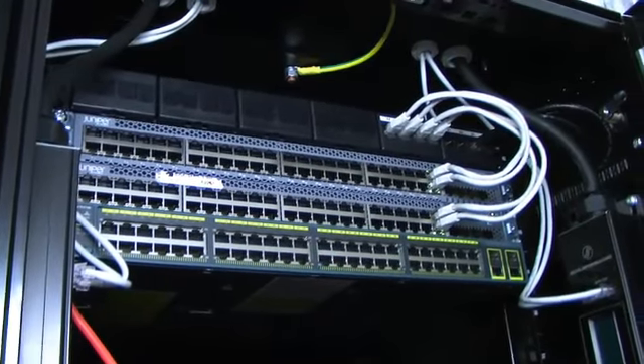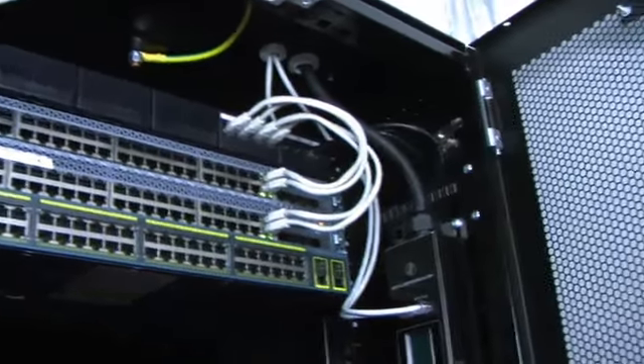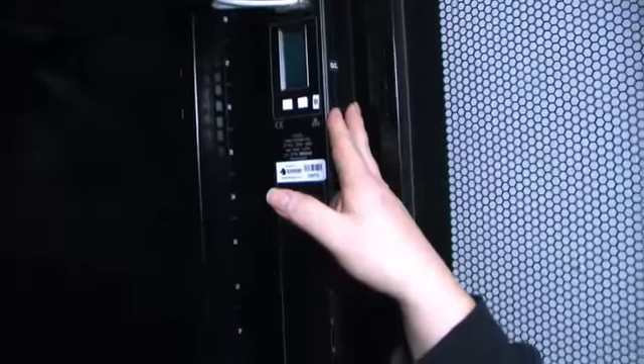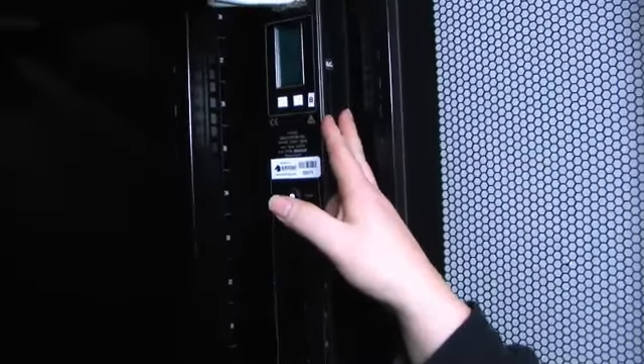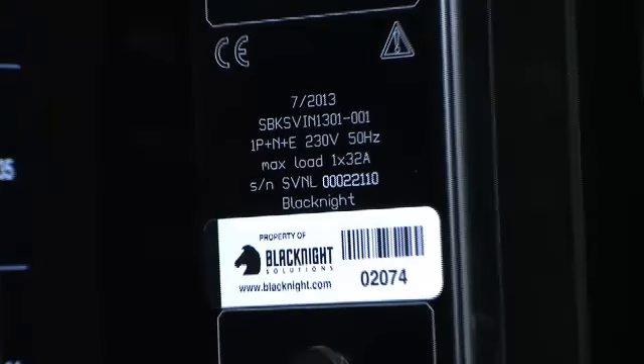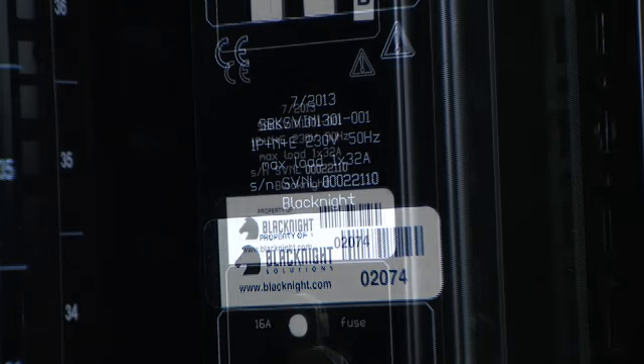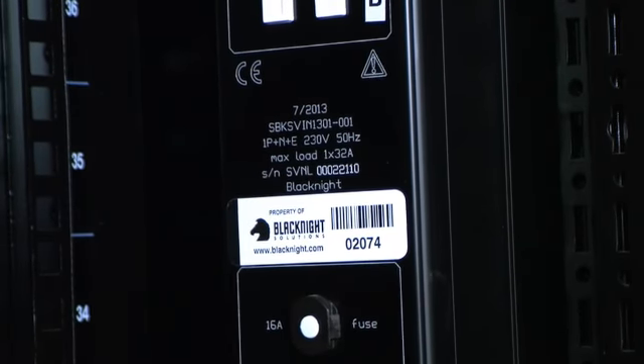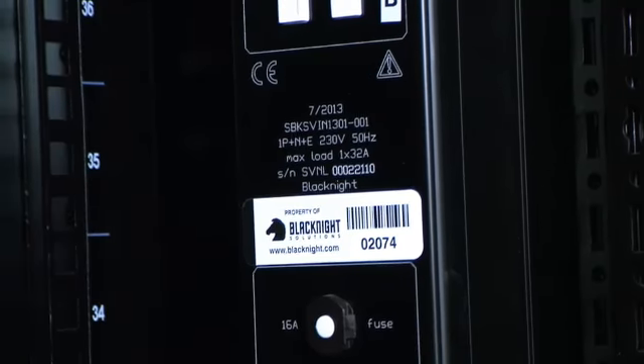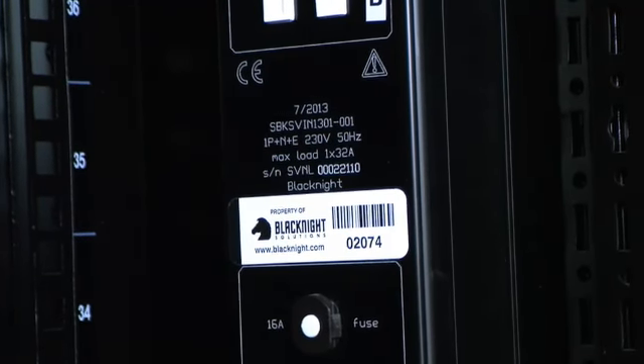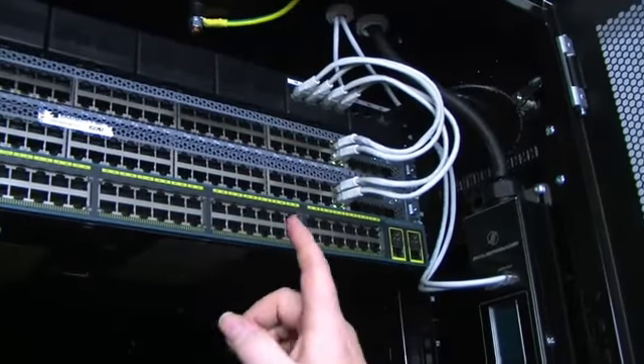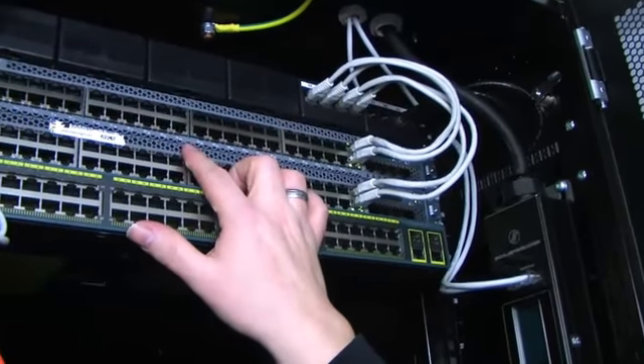And you can also see we have Blacknight branded PDUs, and all of these are centrally wired back to a monitoring system. So we can see kilowatt hours used, the load on each PDU, and we can graph the load of the data center on a per rack and a per pod basis, if that makes sense. So when we install servers here, there'll be up to about 40 servers, and they'll all be wired back into these switches.